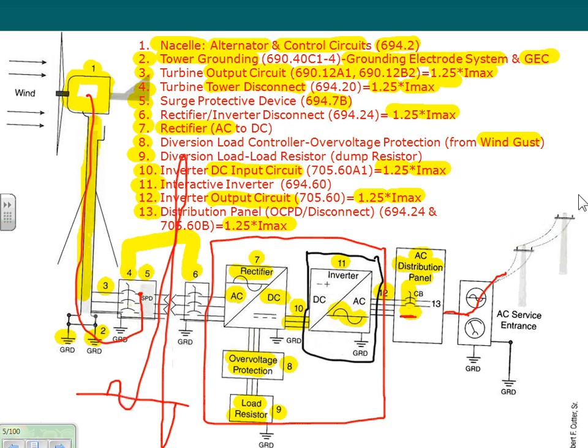So say we have a storm that knocked down the transmission line right here. What's going to happen if you continue to generate power and feed it to the grid? You're going to hurt somebody. That's what they tell us. But if you know how the linemen work, they have a lot of rules that protect them. They just don't want you to generate power back into the system when the system is down, for safety and control and so forth. So this inverter should be able to completely isolate you from the system right in here.